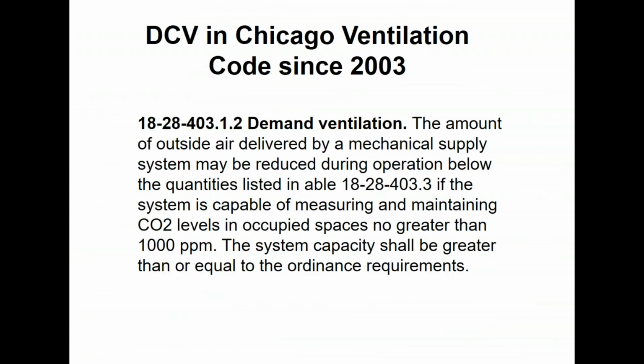The city of Chicago does it a little bit differently, as you would expect. Their CO2 requirements have a fixed set point of 1,000 parts per million. Whereas in other places, we typically do 700 above the outdoor air level. So if it was 450 where you live, it would be an 1,150 set point. But the city of Chicago does not do it that way. They have a flat number of 1,000 parts per million, which is typically less aggressive than other places. But when Chicago set that 15 years ago, it was before ASHRAE had set any standard for it. So Chicago's kind of going out on a limb on their own there.